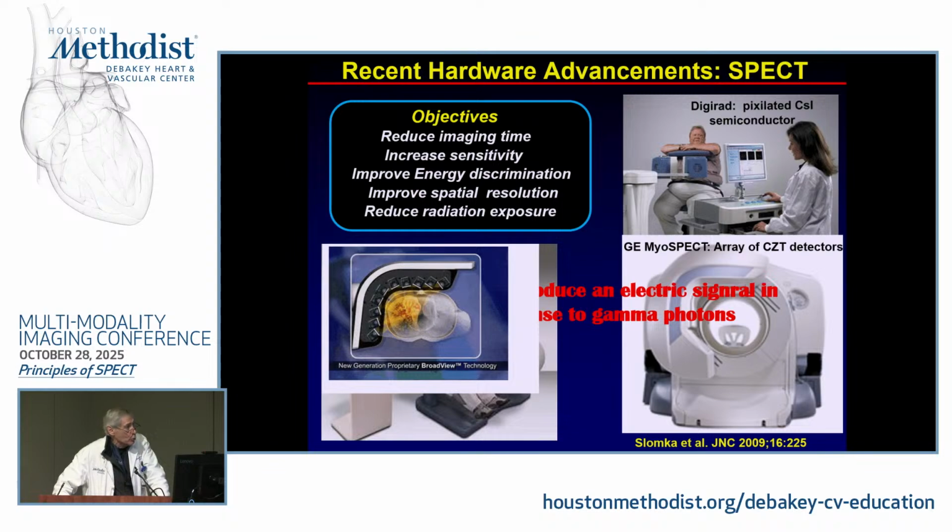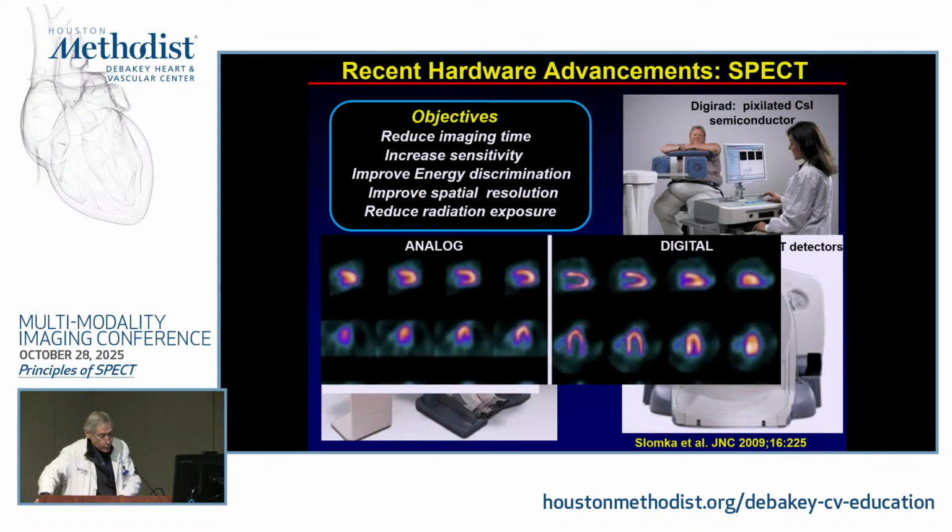And this is just a typical array of what you see. All of these systems now are fixed gantries. As you know, we still have a lot of these rotating gamma cameras that go over 180 degrees. All of the CZT cameras are now fixed arrays over about 120 to 180 degrees. So we lose some specific artifacts by having fixed gantries. But it also allows us to acquire more counts within a given time period.